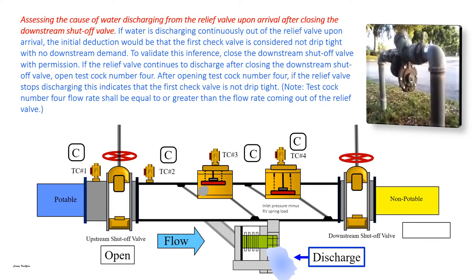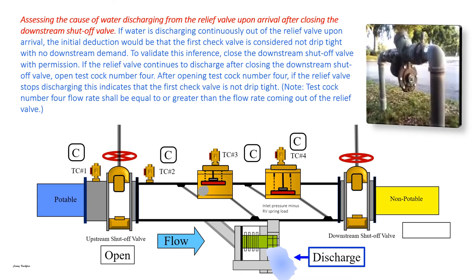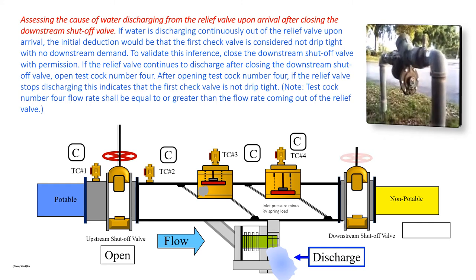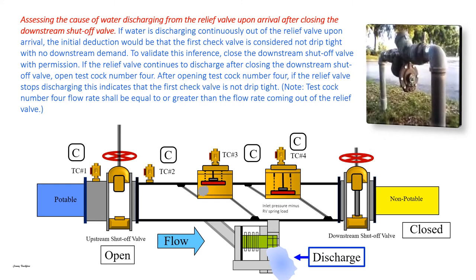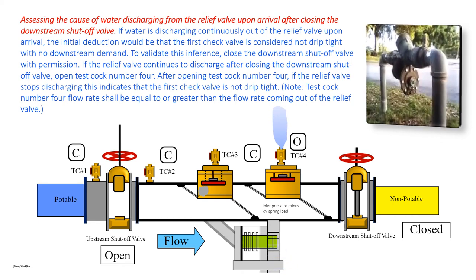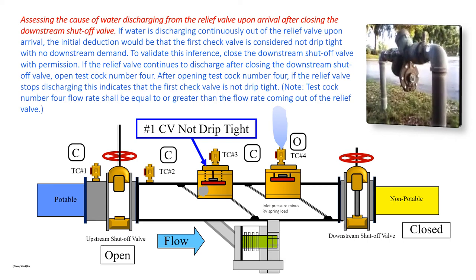Assessing the cause of water discharging out of the relief valve upon arrival after closing the downstream shutoff valve. If water is discharging continuously out of the relief valve upon arrival, the initial deduction would be that the first check valve is not drip tight with no downstream demand. To validate this inference, close the downstream shutoff valve with permission. If the relief valve continues to discharge after closing the downstream shutoff valve, open test cock number four. After opening test cock number four, if the relief valve stops discharging, this indicates that the first check valve is not drip tight. Note: test cock number four flow rate shall be equal to or greater than the flow rate coming out of the relief valve.